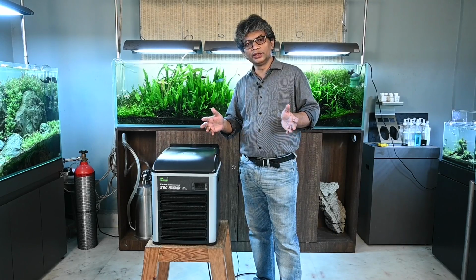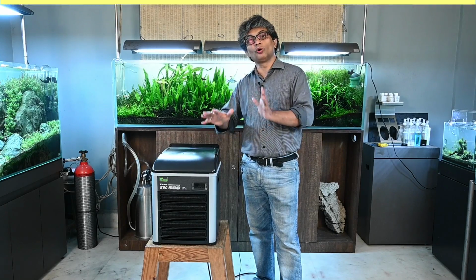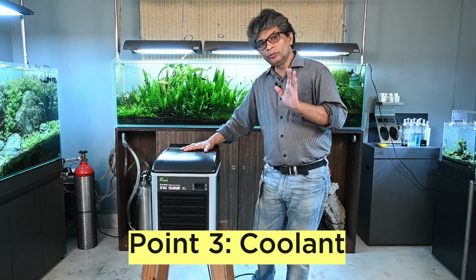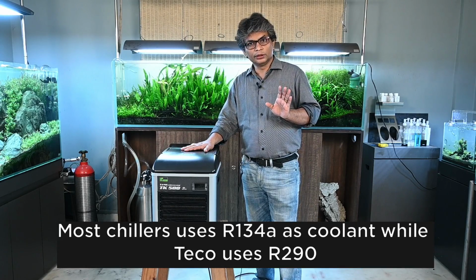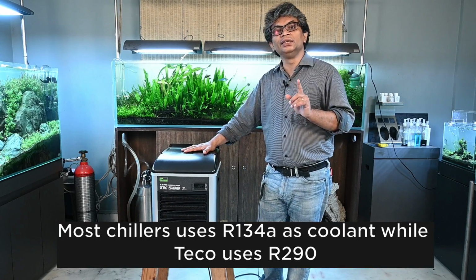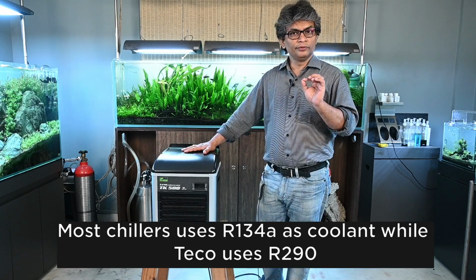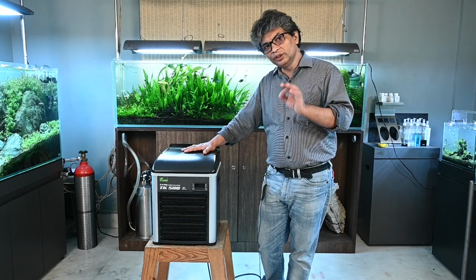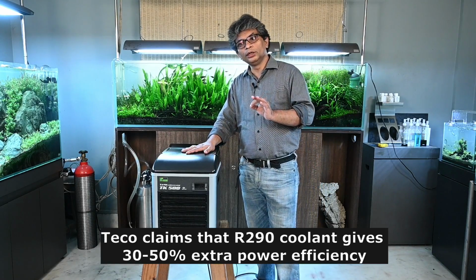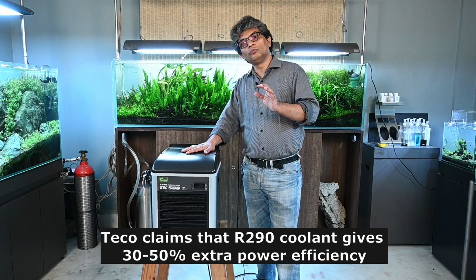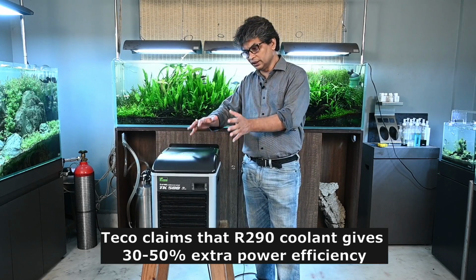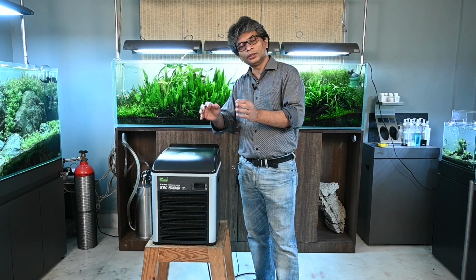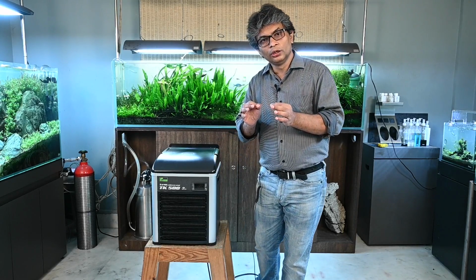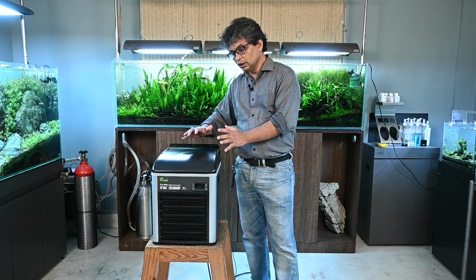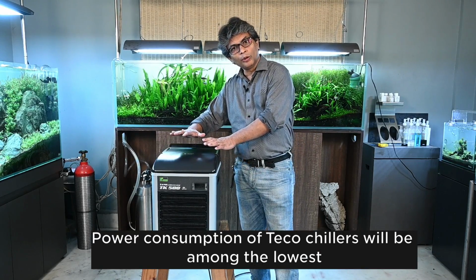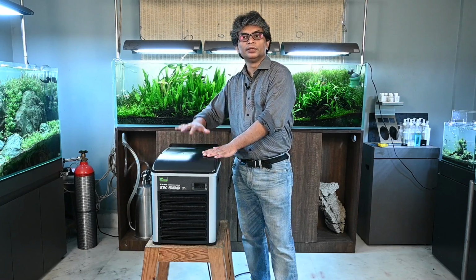So as we are talking about chiller, the next important thing is what coolant is being used. Normal chillers use R134A coolant. Teco TK500 uses R290, which is a much more efficient coolant compared to R134. Teco claims this gives almost 30 to 50% extra power saving. Obviously there are other factors, like the titanium heat exchanger, but the coolant also goes a long way in giving better power efficiency. If you run this chiller continuously, your power consumption will be definitely much lesser than other chiller models.